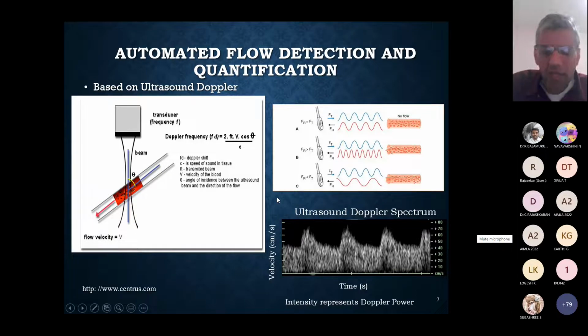So how is this used clinically? Basically, it's the picture in the bottom right. What you're seeing here is, using this extracted Doppler shift, you can now present it like a spectrogram. In a spectrogram the x-axis is time, and the y-axis is frequency, or it can be converted to velocity using this equation. Basically what you're seeing, as a function of time, is the instantaneous velocity, or the distribution of velocities in the image. It's also useful to note that the brightness of each pixel here represents the strength of the Doppler signal. So in a way, this is a three-dimensional representation of the Doppler information, right? The x-axis is time, the y-axis is velocity, and then the power is shown by the magnitude of the intensity of the pixels.